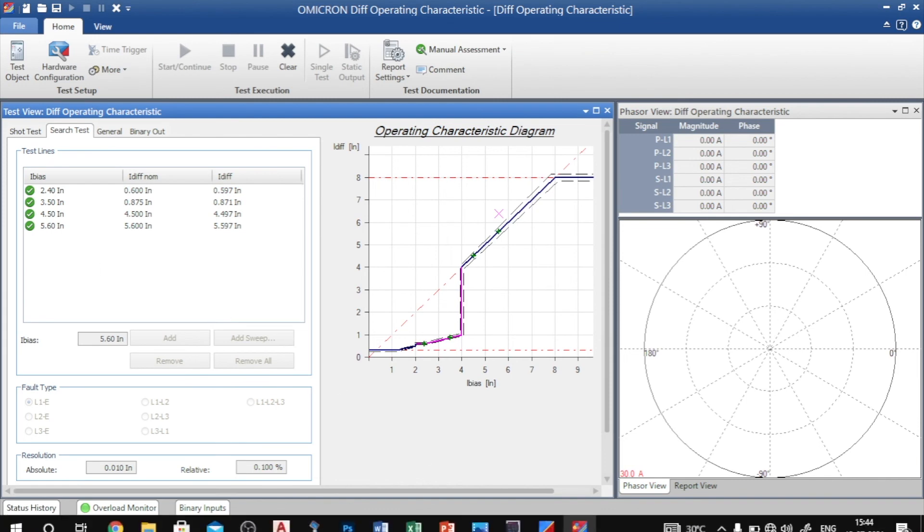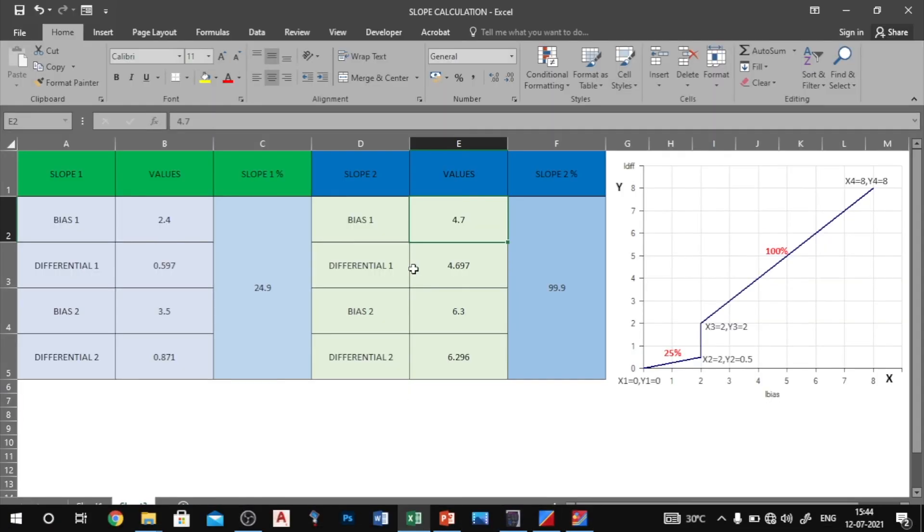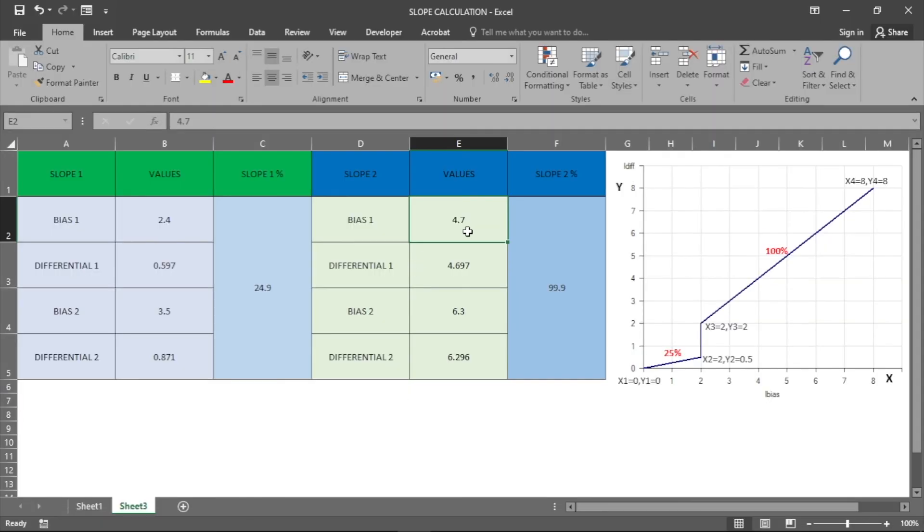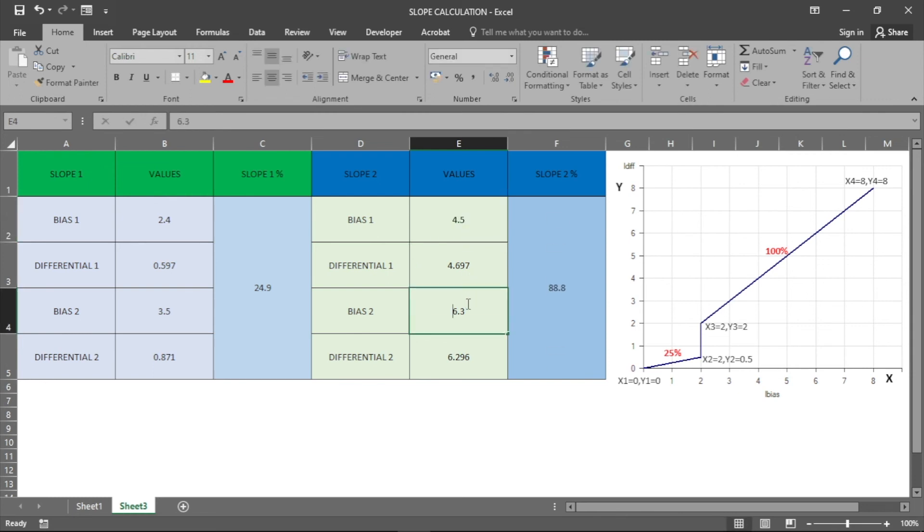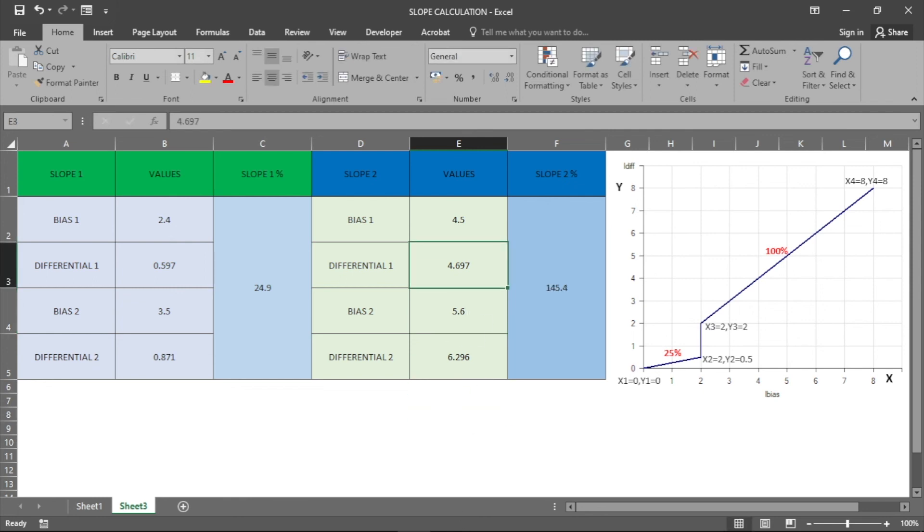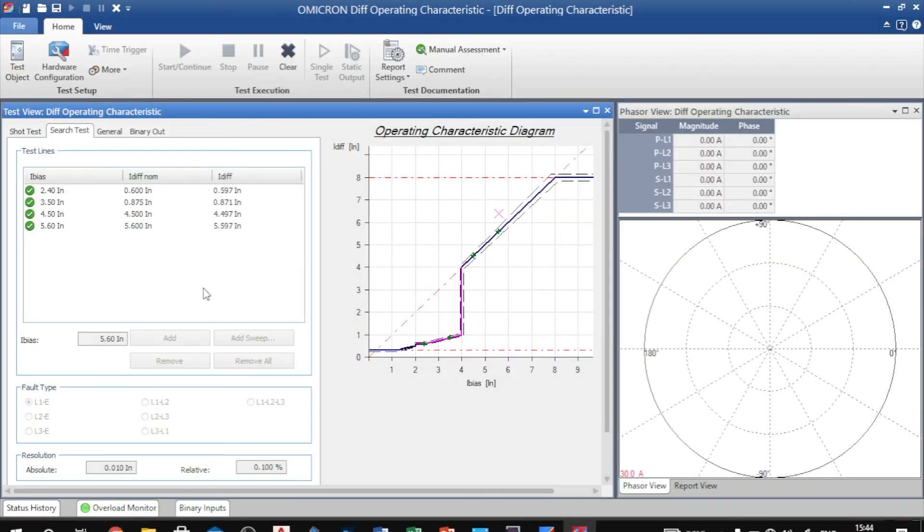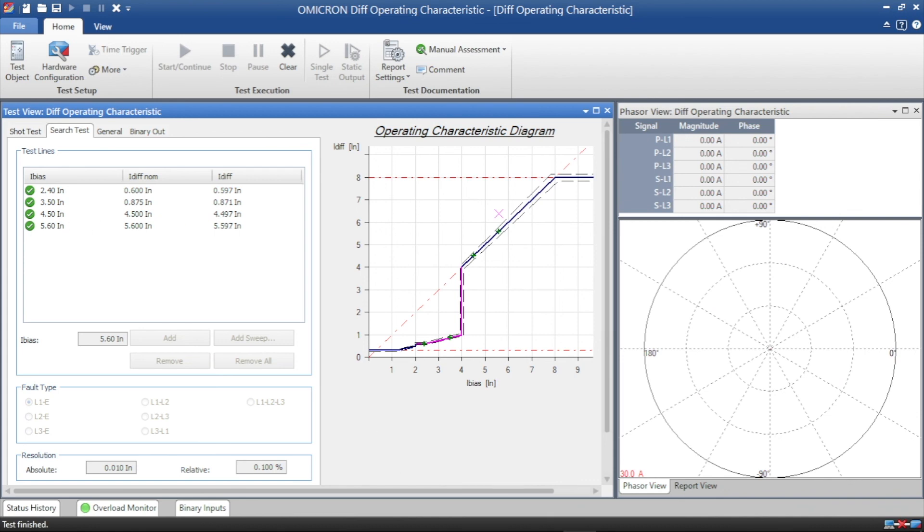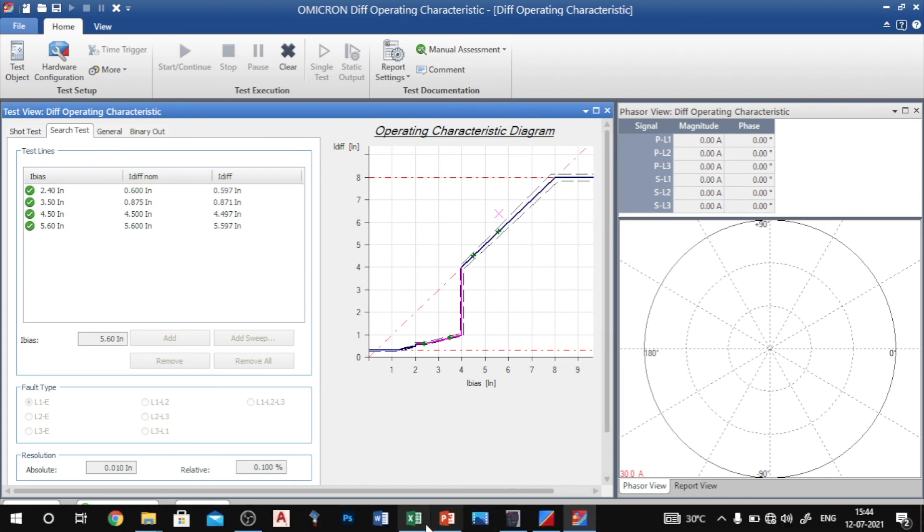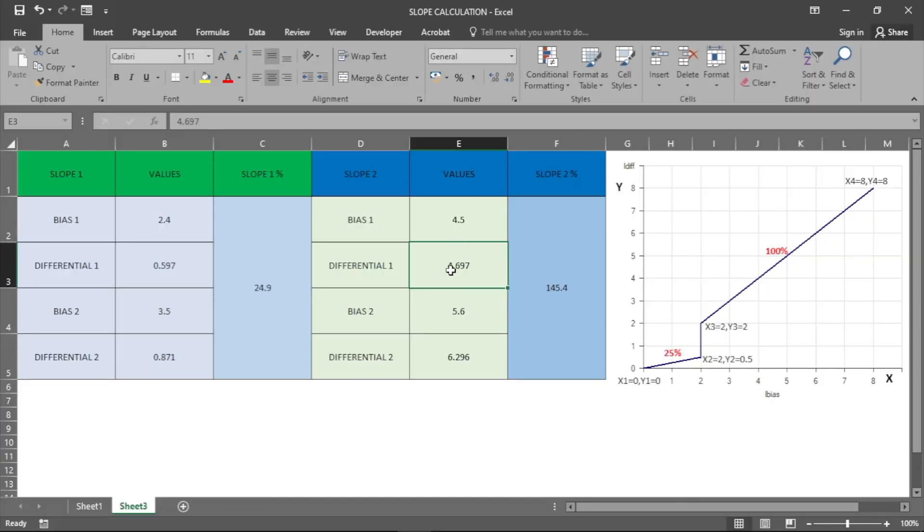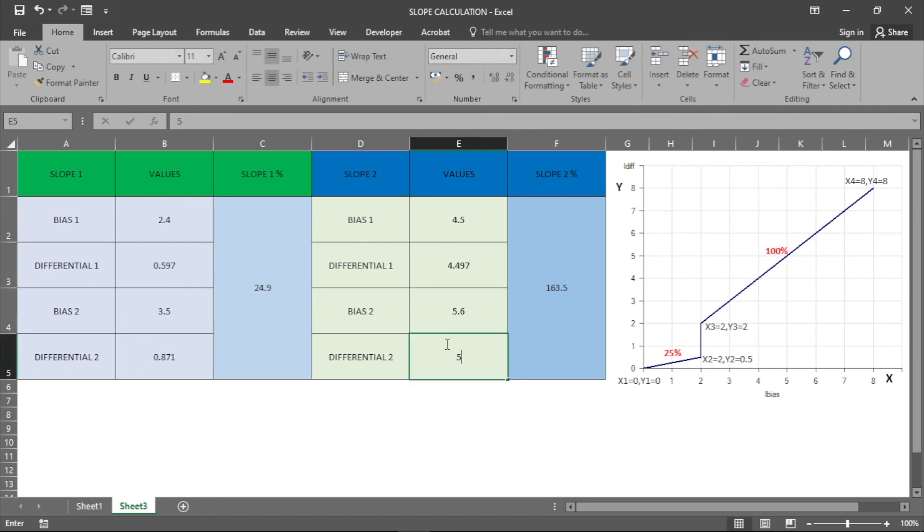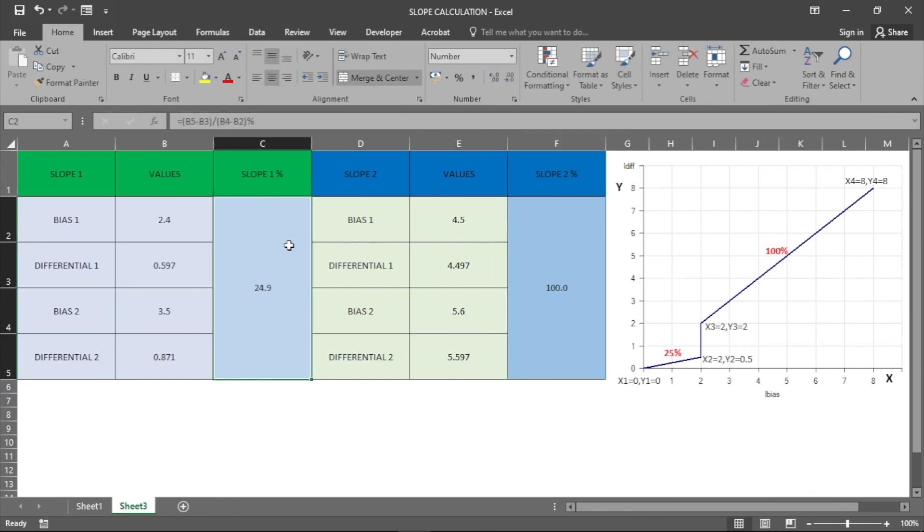I have to enter the bias value first. Bias value is 4.5 for bias 1 and bias 2 is 5.6, and differential 2 value 5.597. Now we got exactly 100% slope.